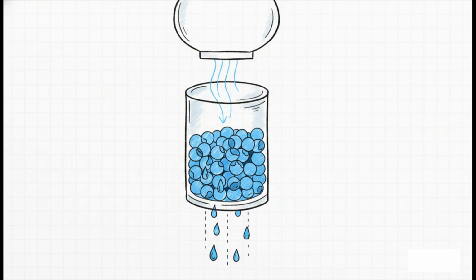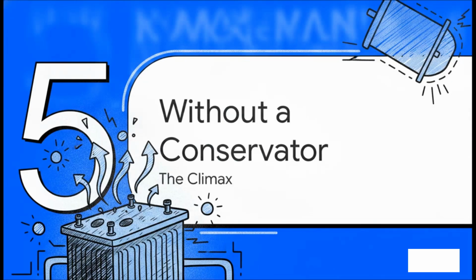Now, outside air carries moisture, and moisture is the absolute enemy of insulating oil. That is exactly why the air is pulled in through a device called a silica gel breather. You've got these specialized particles in the breather stripping away every single drop of moisture, making sure that only perfectly dry air enters the conservator tank to replace the contracting oil. Pretty clever, right? Finally, let's imagine a scenario without a conservator tank, the climax.